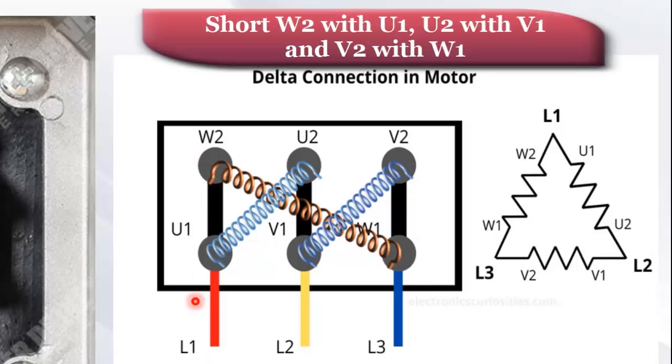Now make straight connections to connect W2 with U1, U2 with V1, V2 with W1, in order to run motor in delta configuration.